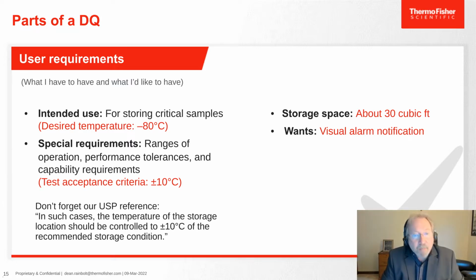Now, special requirements, ranges of operation, performance tolerances, and capability requirements. In this case, I'm going to refer to the USP just for this example. In their general chapters, they say that if you're going to store samples colder than minus 20, you're allowed plus or minus 10 degrees C movement of the recommended storage condition. So my test acceptance criteria is plus or minus 10. I'm also going to need about 30 cubic foot, and I'd like some visual alarm notification. That's just what I want.